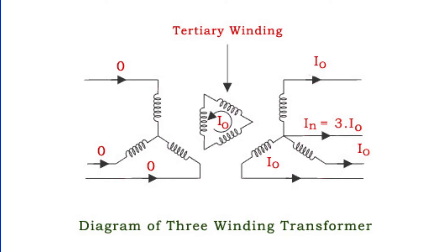In a star-star neutral transformer, the presence of the tertiary winding significantly diminishes the zero-sequence impedance. This ensures that the transformer is well prepared to deal with any imbalances that might transpire, guaranteeing the smooth and efficient operation of the system.